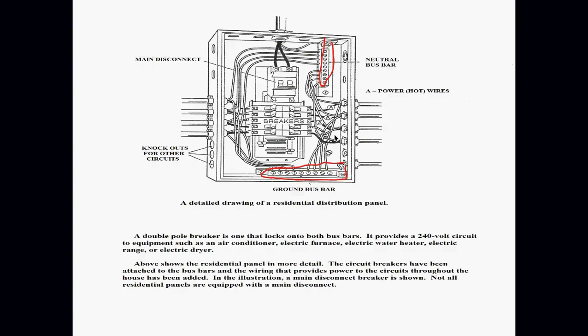There's knockouts for other circuits, but again, you as an HVAC technician, and I need to stress this, are not allowed to do anything inside the breaker panel. That's for your own safety. That's an electrician's territory. Now, do I occasionally have to pull a cover off a breaker panel and take a look inside just to make sure something's wired right? Yeah. Am I supposed to? No. Your job comes from the disconnect or the connection to the equipment. That's where your licensing and your responsibility starts. If my breaker's set properly and I don't have voltage in, or I don't have clean power, that's an electrician.